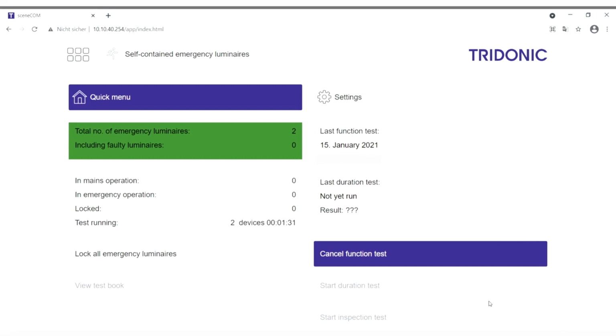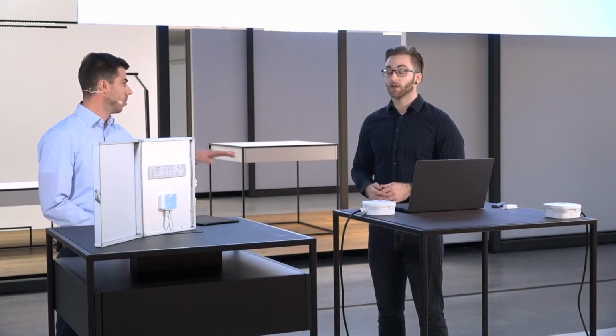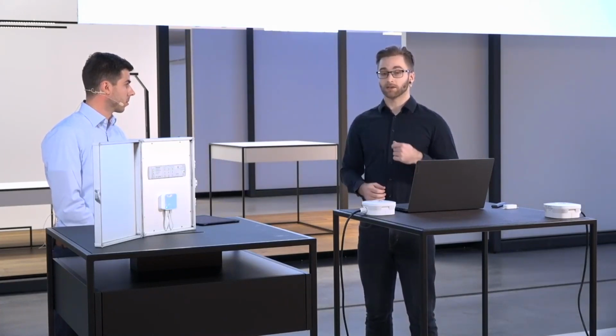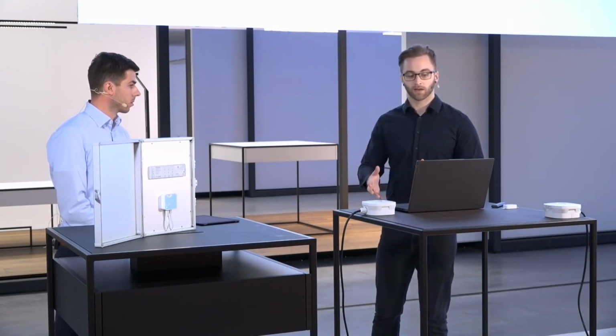So this is the function test, but there's also the duration test. What's the difference? The duration test, as the name suggests, tests the duration of the emergency lighting. The standard durations are either 1 or 3 hours, and it really switches into emergency mode for this desired duration, to check that in case of a mains failure you really have the time to evacuate the building and still have lighting provided.